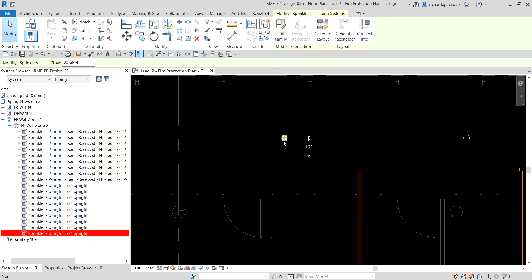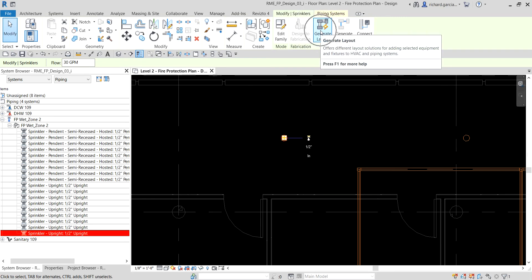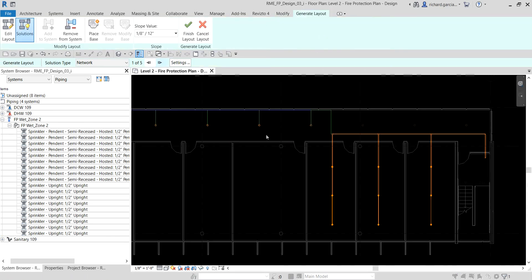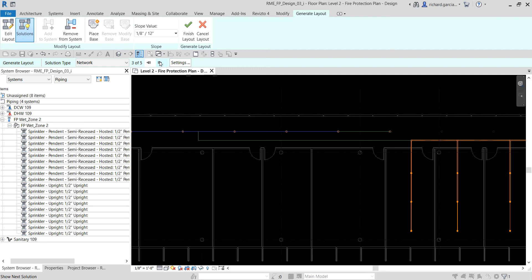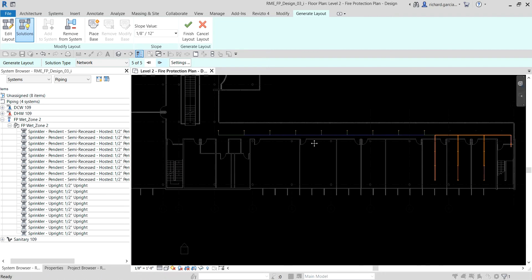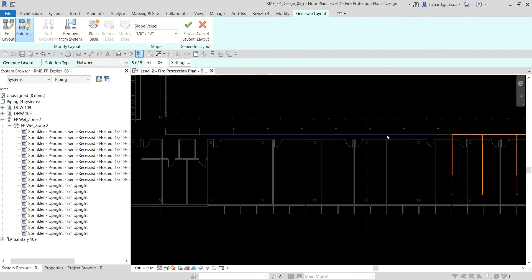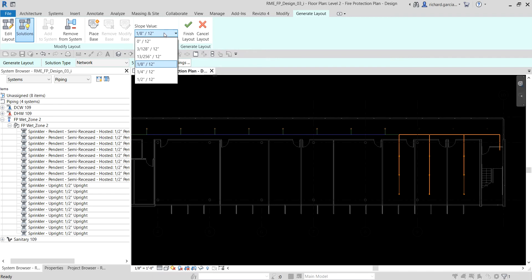I'm going to select one of the sprinklers that is already part of the system and then select Generate Layout. This isn't the layout I want, so I'll use the Network solution — specifically Network 5 of 5. The blue line is the main pipe and the orange lines are the branch pipes. I'll set slope to zero and finish.